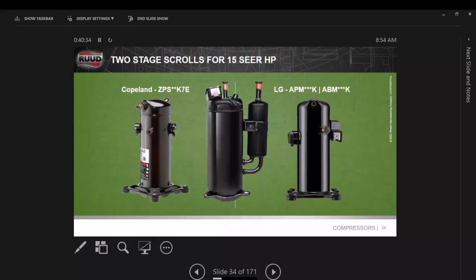The way to determine them is the solenoid. If you look on the outside, this one has an external solenoid. That one's internal. You can change the coil on this one. You can't on the Copeland. So you can't change the valve, but you can change the coil on it.